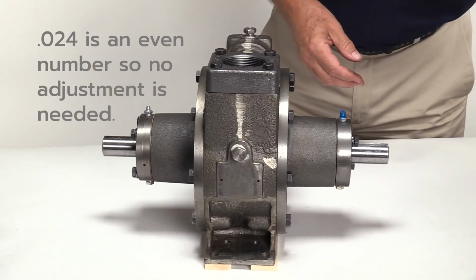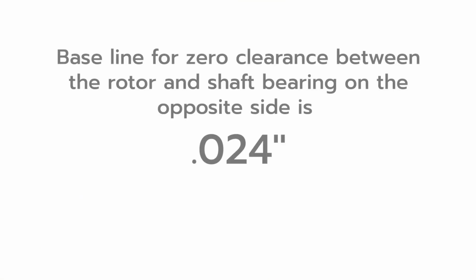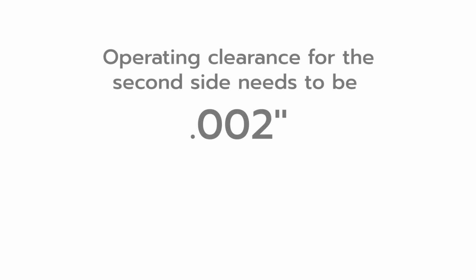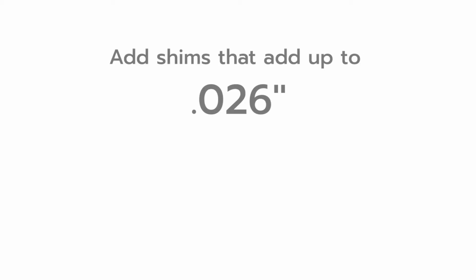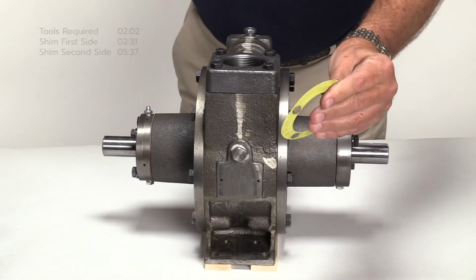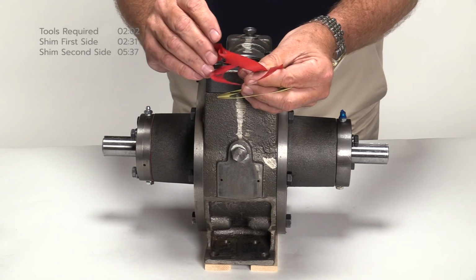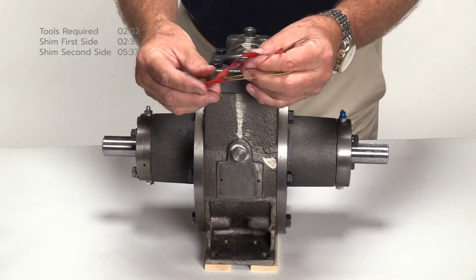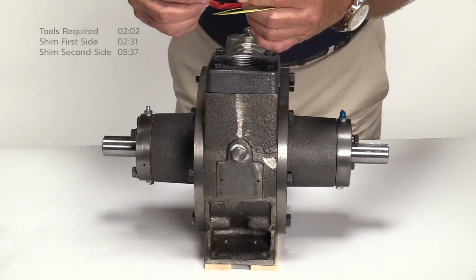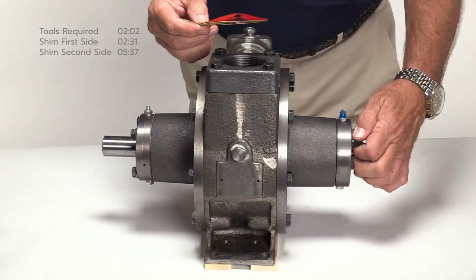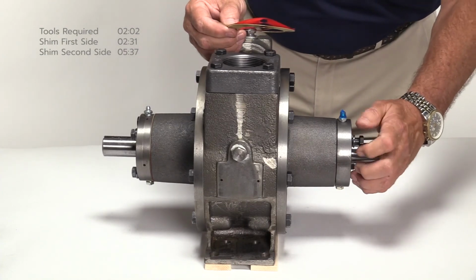So in this case, the baseline for zero clearance between the rotor and shaft bearing on the opposite side is 24 thousandths. The operating clearance for the second side needs to be 2 thousandths. To establish the operating clearance of 2 thousandths, add shims that bring the total amount of clearance between the bearing cap and the pump head to 26 thousandths. 24 thousandths baseline clearance plus 2 thousandths equals 26 thousandths worth of shims that need to be added. Shim the pump using a combination of shims totaling 26 thousandths. In this example, use 1 yellow 20 thousandths shim and 3 red 2 thousandths shims to accomplish 26 thousandths worth of shimming. Remove the bearing cap and add the 26 thousandths shim pack.